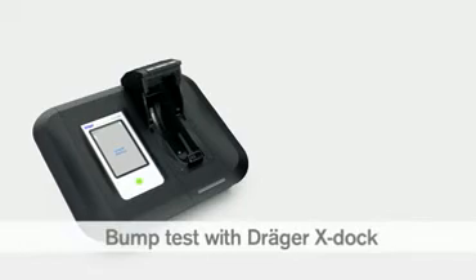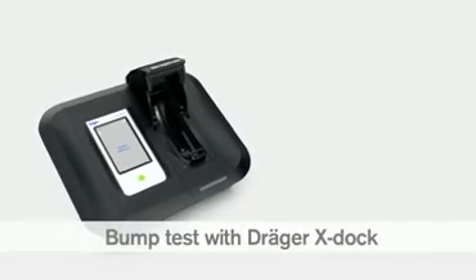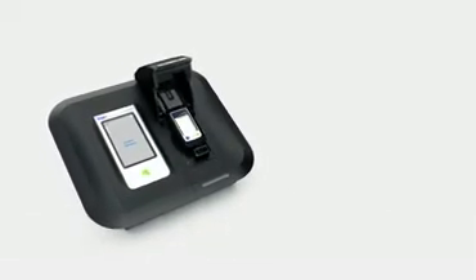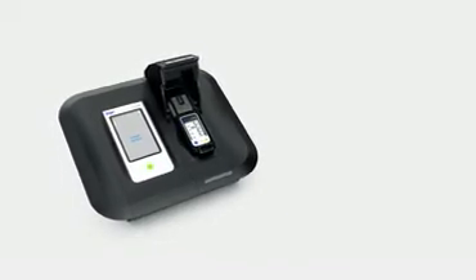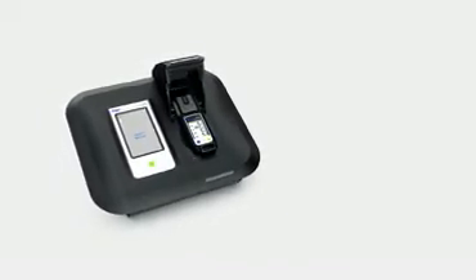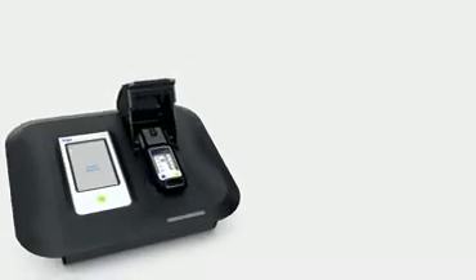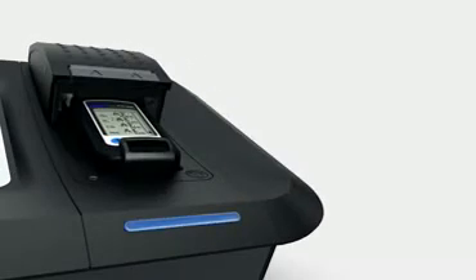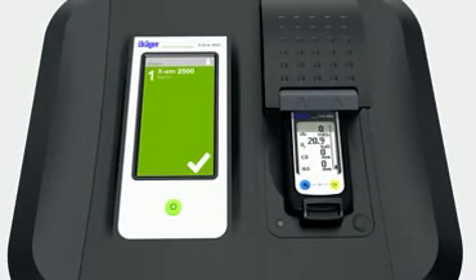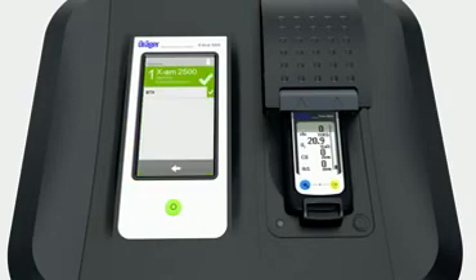You can also carry out a bump test with a Dräger X-Dock station. Place an instrument inside the module. When you do so for the very first time, the Dräger X-Dock recognizes the device and logs it in its integrated database. The LED strip flashes blue. When the LED changes to green, the test has been completed successfully. The X-Dock screen also turns green. Touch it to obtain additional information on the test results.